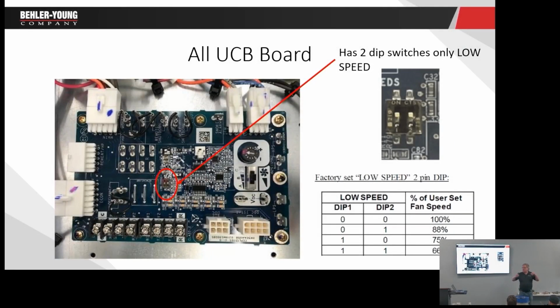All right, I want to eliminate that for whatever reason. We need more airflow during circulation. I can simply turn those switches off and bring it up to 100%. You'll notice when this thing comes out of heating and the blower shuts off from heating, all of a sudden you hear the blower slow down because it goes to that circulation speed. So the other set of dip switches, which both boards have, has to do with what the circulation fan speed is, the R to G. That as well is on the tag by the wiring diagram.